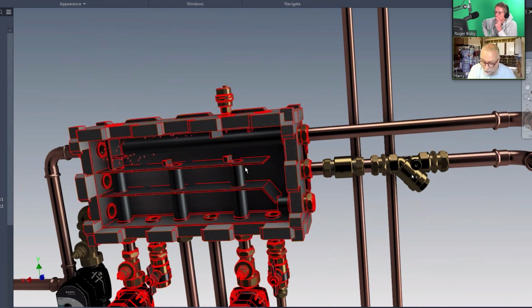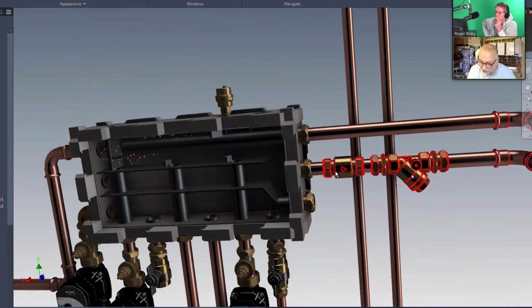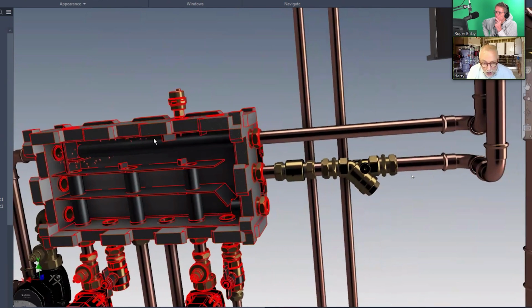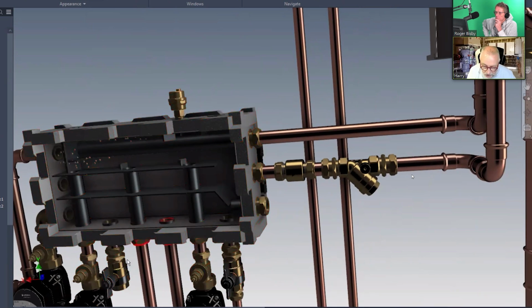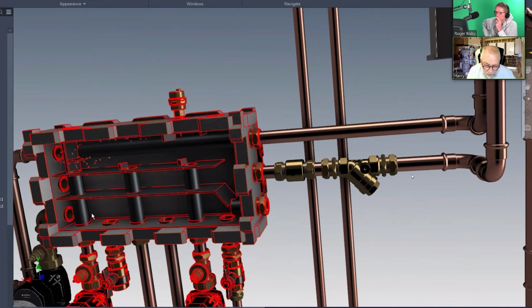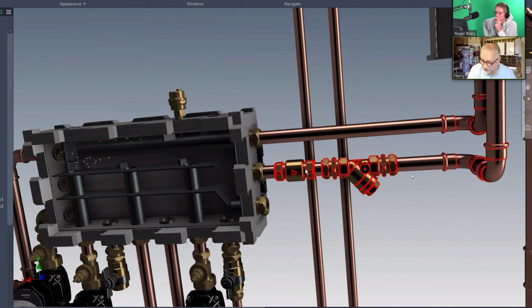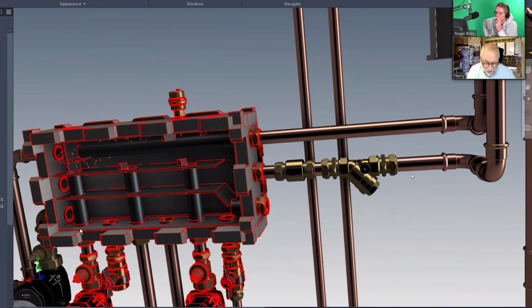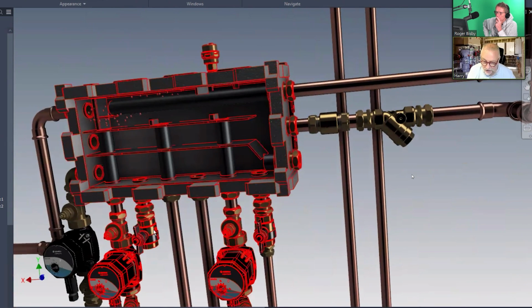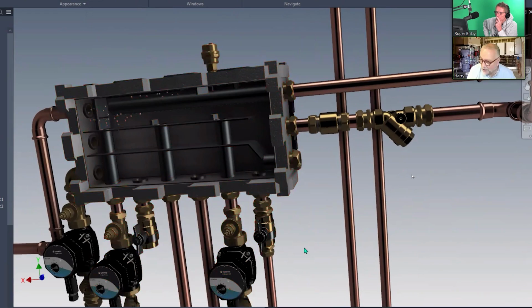This is the overall system's neutral point. When it gets to here, this is taking back the hottest water. The coldest water is coming back from the zones down to here, and can be taken by the heat pump, whereas the stove can take the hot water that's left over from passing the zones. So the stove is working at a high temperature, whereas the heat pump predominantly is working on the zone return water, so that can operate away.